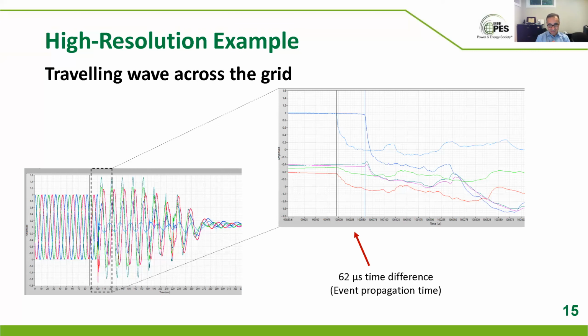When the time difference between the wave arrivals at the two ends is 62, that tells me the fault must have happened at 9 microseconds from one side and 71 microseconds from the other one. 9 and 71 together make 80 microseconds, okay? And the difference between 9 and 71 is 62, right? So if a fault happened at that point, 9 versus 71, then 9/80ths, or about 11% of the line length, is where the fault happened. 11% from the terminal that shows it first, and of course, 89% of the length of the line from the other.